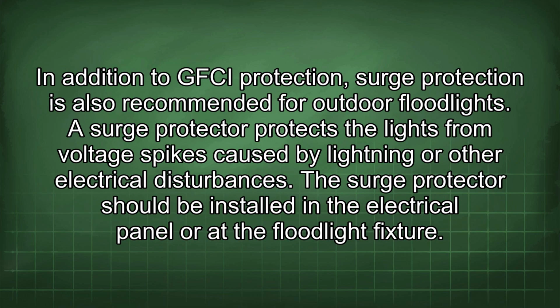In addition to GFCI protection, surge protection is also recommended for outdoor floodlights. A surge protector protects the lights from voltage spikes caused by lightning or other electrical disturbances. The surge protector should be installed in the electrical panel or at the floodlight fixture.